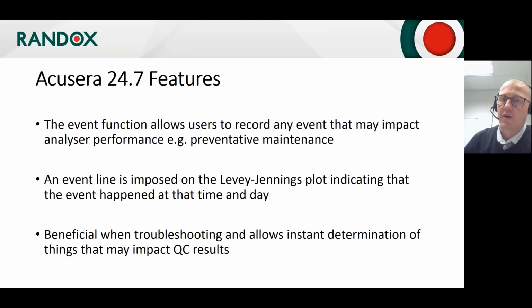It also allows you to create what we call events. So these are times where it will put a line on the graph, and it'll indicate that you've had some maintenance done, or calibrations, or a change of lot number. I mean, essentially it's free text, so anything that you want to write in, you can put in. This is then imposed on your Levey-Jennings plot. So you've got a permanent record of which maintenance was carried out when, which calibration was carried out when. Again, this is a great benefit if you're troubleshooting, as it allows an instant determination of things that may have impacted your QC results, such as a reagent lot change, such as a failed calibration, such as a PMI visit.